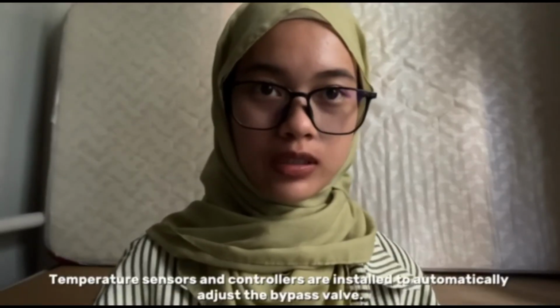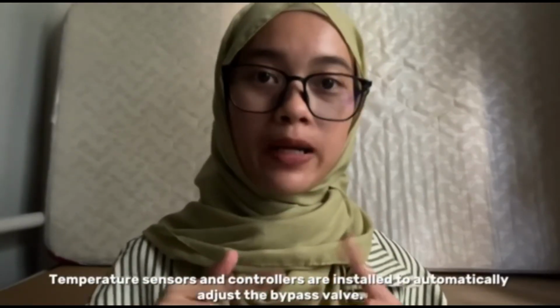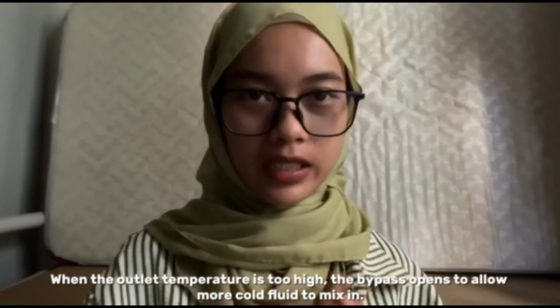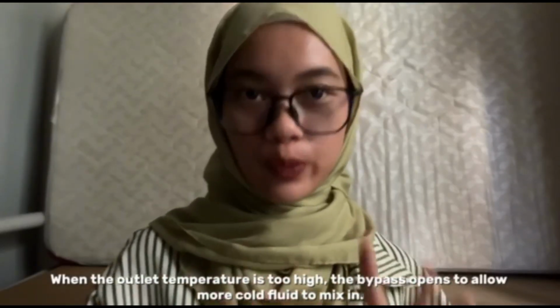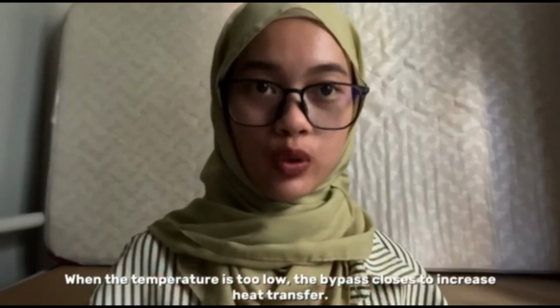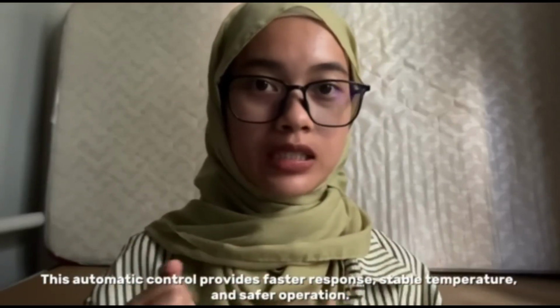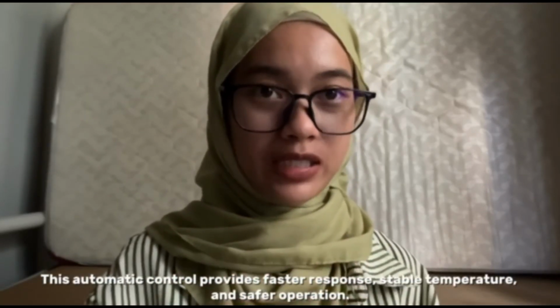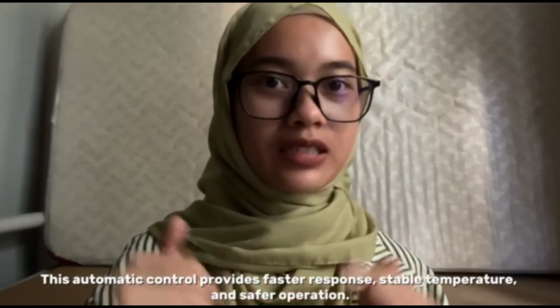Temperature sensors and controllers are installed to automatically adjust the bypass valve. When the outlet temperature is too high, the bypass opens to allow more cold fluid to mix in. When the temperature is too low, the bypass closes to increase the heat transfer. This automatic control provides faster response, stable temperature, and safer operation.